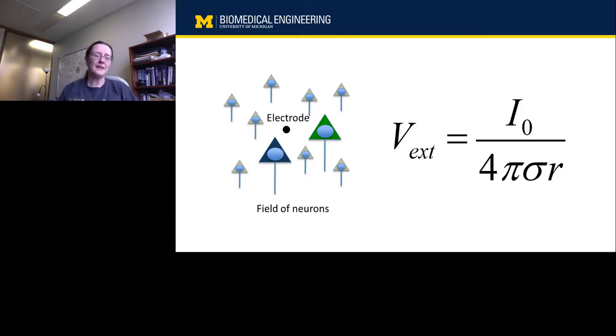So the impedance associated with the scar isn't necessarily a big problem. We can handle the impedance of the electrode. The big problem that we have, however, is the distance. As a scar forms, it's going to push those electrodes away. And as you see from the equation, the voltage is inversely proportional to the distance R. And 1 over R means that the signal falls off extremely quickly as we move away from the electrode.